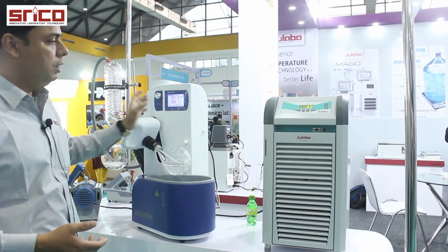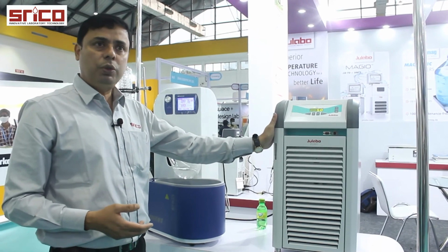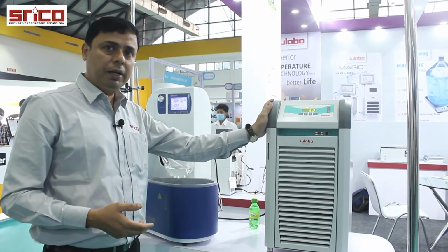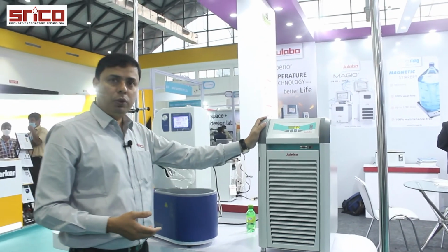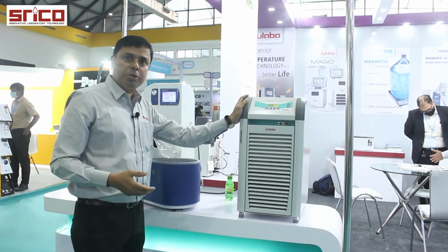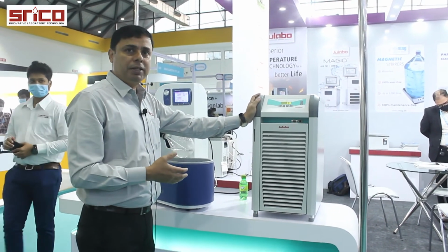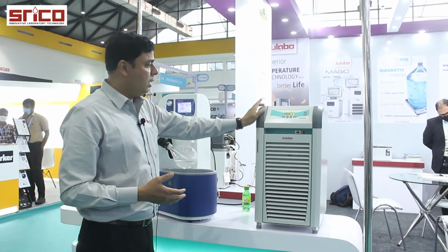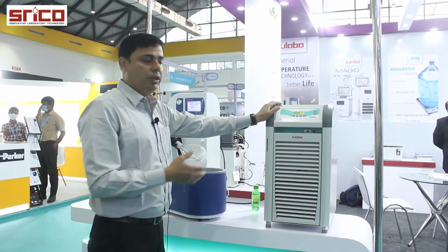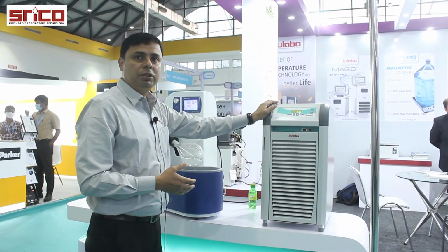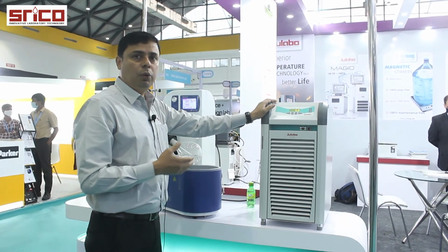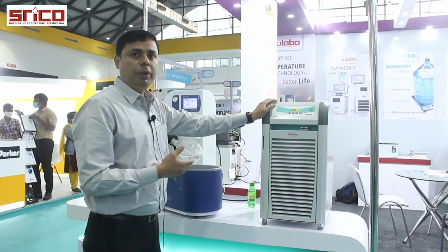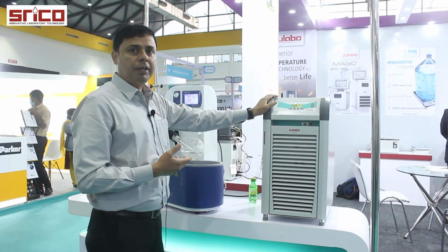And this is again the Julabo chiller that is meant for this rotavap application to cool down this condenser. This temperature range is from minus 20 up to 40 degrees centigrades. We have still smaller size chillers, F250 model, which can cater up to minus 10 degrees centigrades. And this Julabo is manufacturing not only the small chillers, we have chillers even up to 20 kilowatt cooling power, which we are providing for the vaccine production also.